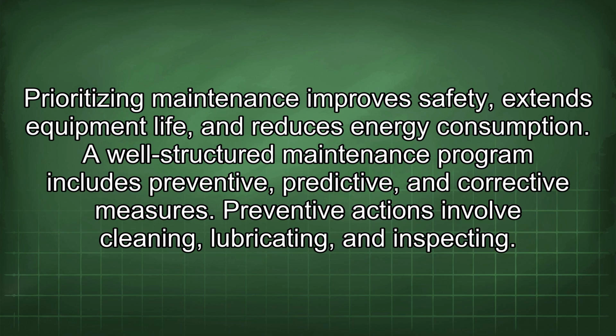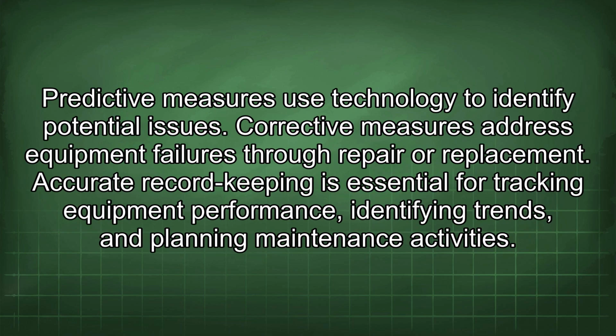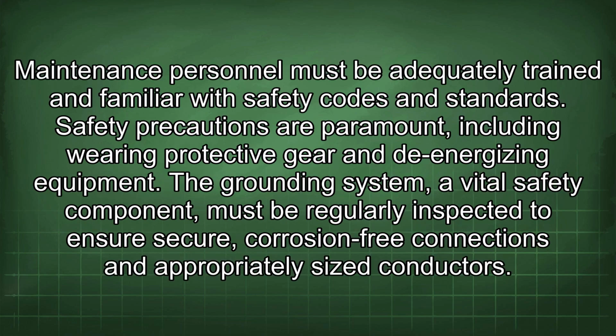A well-structured maintenance program includes preventive, predictive, and corrective measures. Preventive actions involve cleaning, lubricating, and inspecting. Predictive measures use technology to identify potential issues. Corrective measures address equipment failures through repair or replacement. Accurate record keeping is essential for tracking equipment performance, identifying trends, and planning maintenance activities. Maintenance personnel must be adequately trained and familiar with safety codes and standards. Safety precautions are paramount, including wearing protective gear and de-energizing equipment. The grounding system, a vital safety component, must be regularly inspected to ensure secure, corrosion-free connections and appropriately sized conductors.